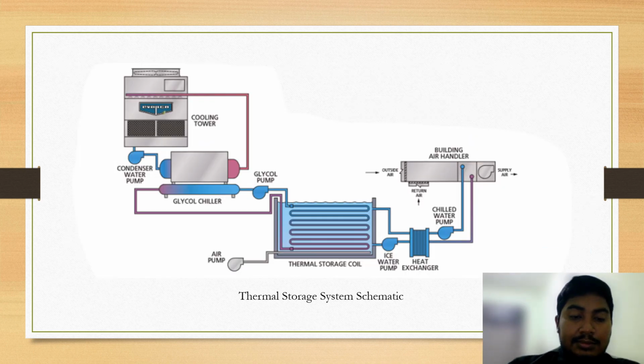So this is a thermal storage system schematic. As we can see, the thermal storage coil will supply cool water to the heat exchanger. So the heat exchanger will supply to the chilled water pump going to the building air handler. So the supply air will become cooler, and then the water that has been supplied will be returned to the heat exchanger, and the heat exchanger will supply to the ice water pump going to the thermal ice storage.